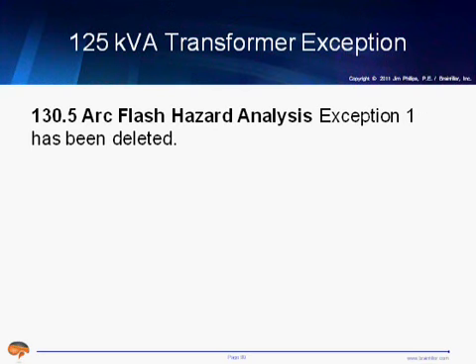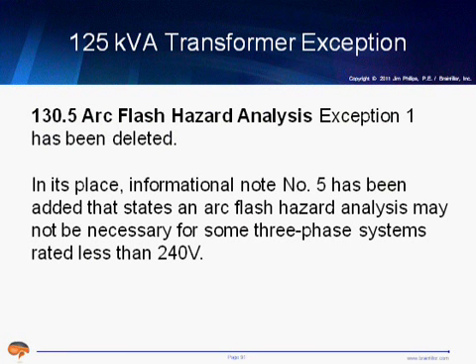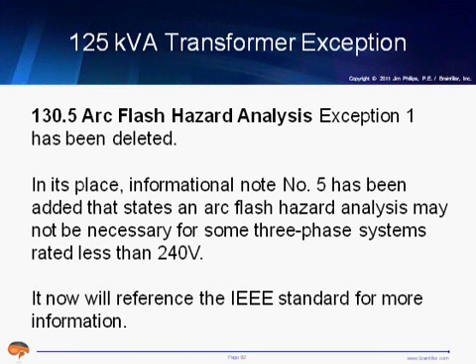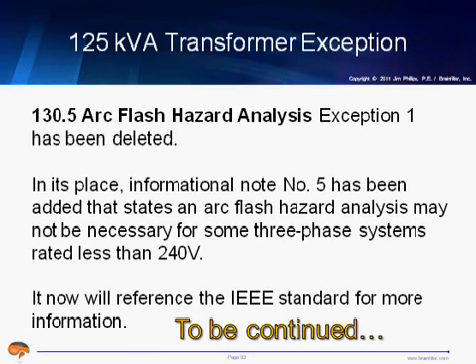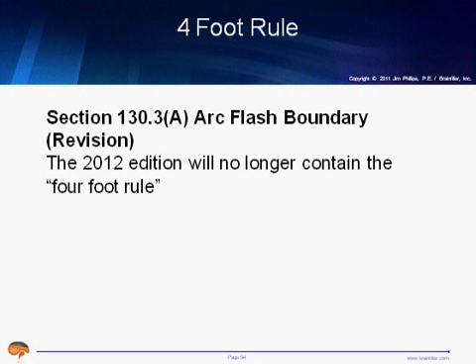In 130.5, beginning in 2012, NFPA has simply deleted the exception. And you may think, well, okay, but now what? Well, in its place, they're saying that you still may be able to exclude certain low voltage, low current systems from the study, but they just refer to or default to IEEE 1584. So as we learn more and things change, IEEE 1584 will reflect the direction to take all this. I say to be continued because we are going to be talking a little bit more about this coming down the road.